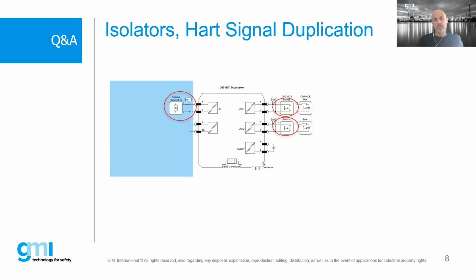So duplicators are quite used in the market for sending the signal to two different places, to different analog input cards, or maybe output also. Or to split the signal that goes to the safety system and another one versus the DCS. And probably the signal has to carry the HART in both cases. In some cases you have just one channel transferring HART, but this module transfers the HART on both channels. Massimo, do we have a live question to answer or not?